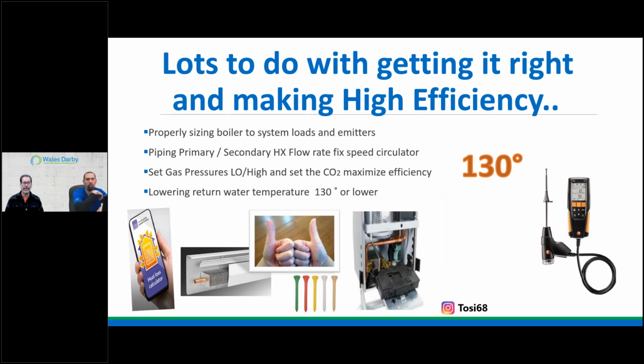So yeah, lots to do with getting it right and making high efficiency, right? First thing is I've got to buy into lowering water temperature. Something that mounts on the wall says it's condensing and high efficiency. Well, it doesn't really start until 130 and lower. All right, do a heat loss. Again, we've got to put envelope over equipment. We have to understand what our requirements are, room by room, zone by zone, or even whole house.